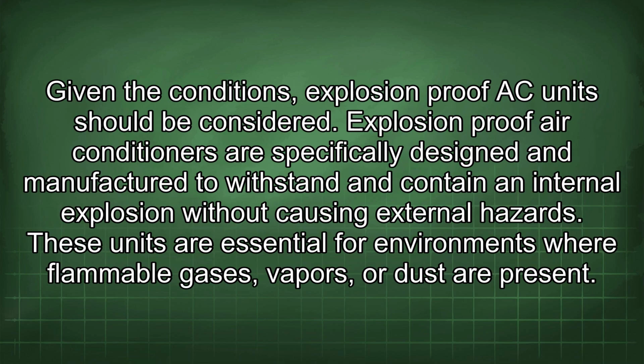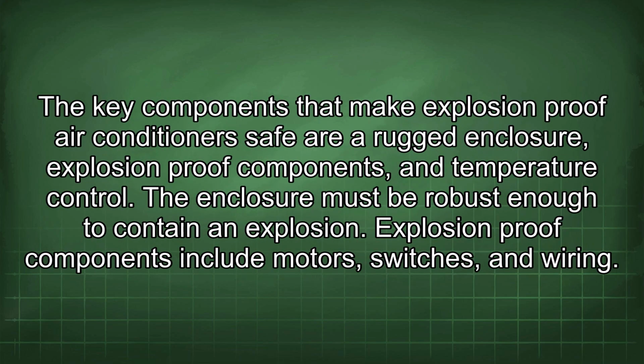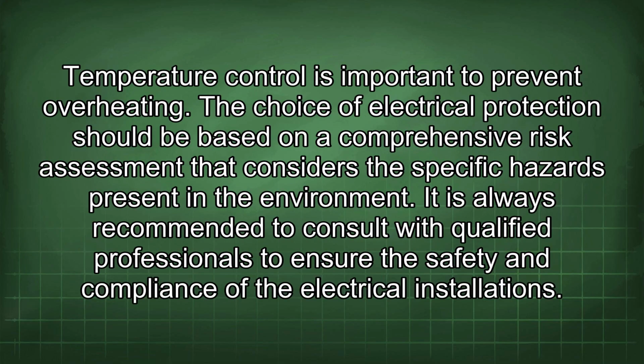Given the conditions, explosion-proof AC units should be considered. Explosion-proof air conditioners are specifically designed and manufactured to withstand and contain an internal explosion without causing external hazards. These units are essential for environments where flammable gases, vapors, or dust are present. The key components that make explosion-proof air conditioners safe are a rugged enclosure, explosion-proof components, and temperature control. The enclosure must be robust enough to contain an explosion. Explosion-proof components include motors, switches, and wiring. Temperature control is important to prevent overheating.